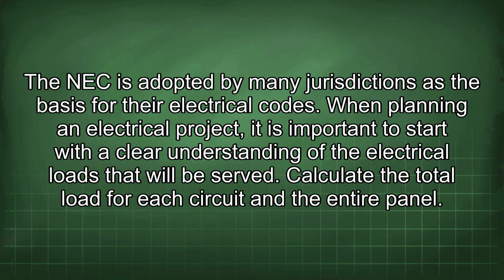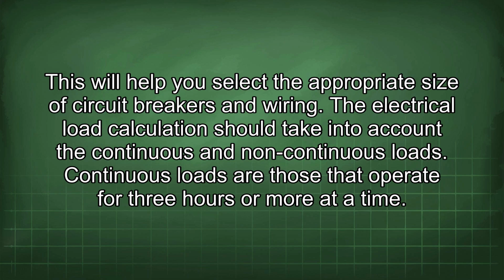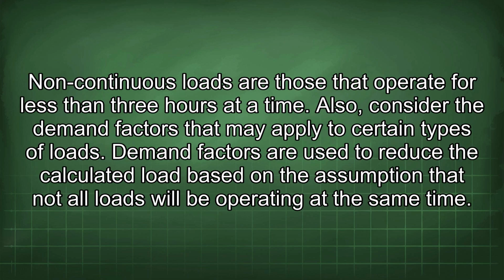When planning an electrical project, it is important to start with a clear understanding of the electrical loads that will be served. Calculate the total load for each circuit and the entire panel. This will help you select the appropriate size of circuit breakers and wiring. The electrical load calculation should take into account the continuous and non-continuous loads. Continuous loads are those that operate for 3 hours or more at a time. Non-continuous loads are those that operate for less than 3 hours at a time.